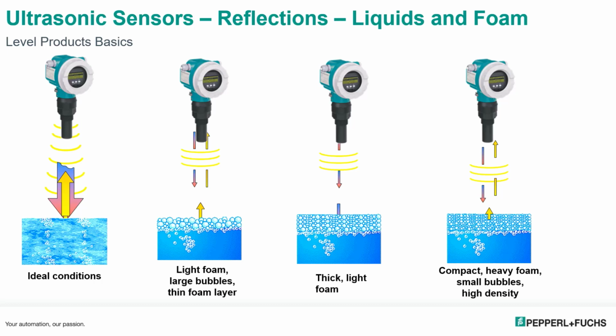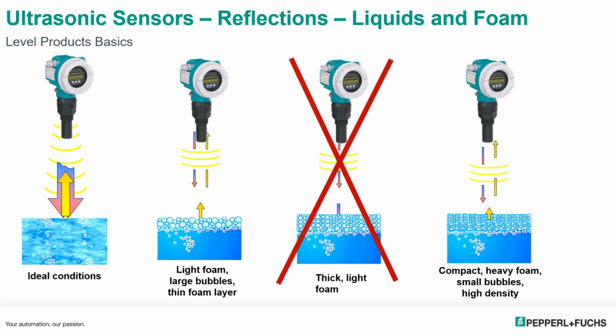Ideal conditions is a completely smooth, hard liquid surface. Even if you have light foam or large bubbles, it can still bounce off there, but there's a point where it will not give a good signal back. And as you can see here, if it's a thick, light foam, then it probably won't give a good signal back and you'll lose the signal in the top layer of that medium. But everything else, it gives you a pretty good signal back.